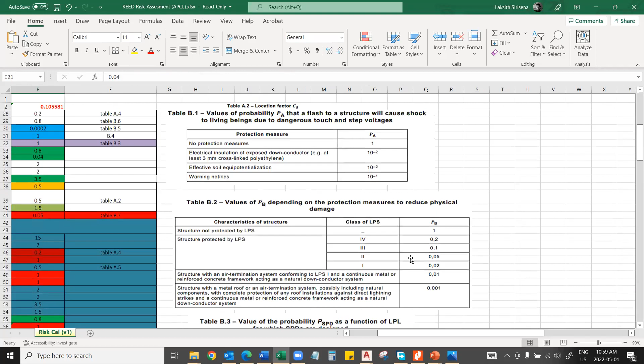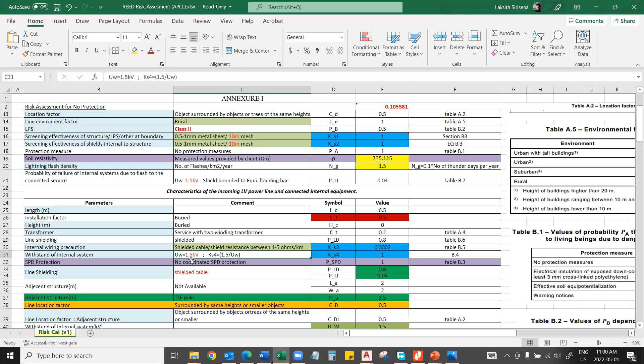And if you have low voltage services, you have to consider the length of the line and how it's installed, if it's buried or overhead. Depending on that, your factor will be varied. And what sort of transformer and how the shielding of cable is done, and also the withstand levels of your equipment. If you have sensitive equipment, it's like 1.5 kV. You can refer these values also with BS 7671 standard. The minimum withstand values you shall maintain, and you have to keep in mind when designing a system is given in BS 7671 regarding low voltage part.